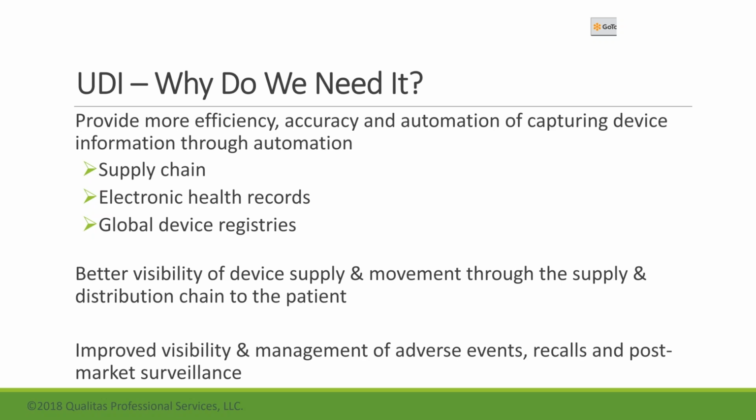And also, what a lot of people tend to forget is that as a medical device manufacturer, you can use UDI internally for your own purposes as well, to help you track, to help you connect, for example, documentation to a device and so on. So it's a powerful tool. It has more power to it than what's actually included in the barcode itself. So it's all in the application.